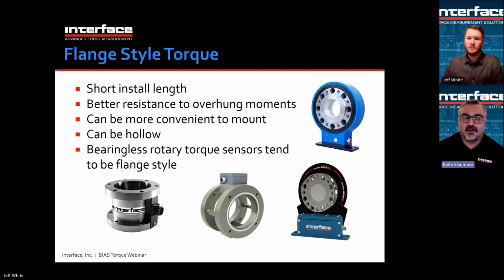So flange style, as we said, has a short installed length and better resistance to overhung moments. Plus, because it's shorter, the actual overhung moment due to mass hanging on the drive line can be significantly less. It can be more convenient to mount, although it's not as easy to find couplings for flange style sensors as it is for shaft style sensors. So you may have to make adapters and things. It can be hollow, which can be useful. Bearingless rotary torque sensors tend to be flange style.